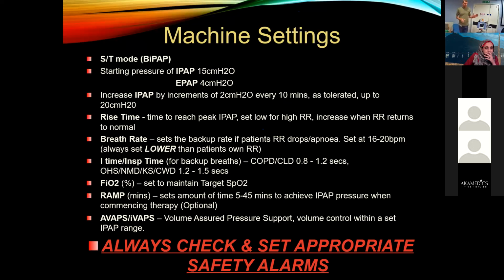And then both devices, so ResMed and Respironics, we have an option within BiPAP called AVAPS in Respironics machines, or in your ResMed machines, it's iVAPS. But this is basically an alternative way of delivering your therapy. So in AVAPS or iVAPS, this is a volume assured pressure support. So it's volume control within a set range of inspiratory pressure.